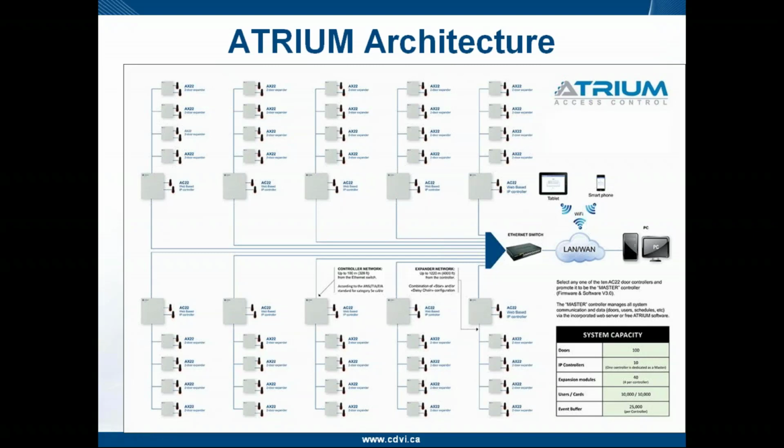So, bits of information. When I connect to the system, just to make sure we understand correctly, I have multiple controllers here. I have a 100 door system. When I log into the system and I add a card, when I enter my login ID, username, and password, I'm connecting to the master controller. Now the master controller will then, if I add a card, when I click save, send the copy of that data to each subcontroller in the system.